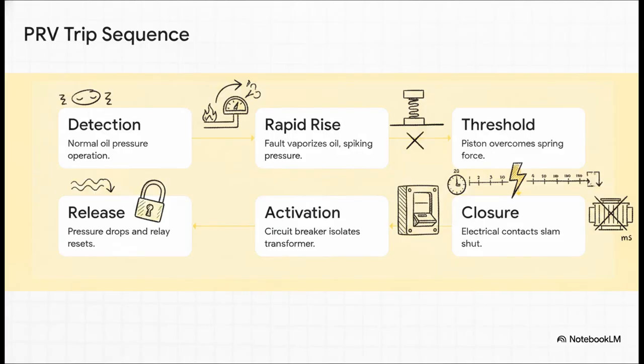Because it's so fast, the PRV has to progress through 6 precise stages in an absolute flash. It starts in a dormant detection state, jumps into action during that rapid pressure rise, and decisively pushes past the spring's physical threshold. Once it crosses that line, boom, the piston slams the electrical contacts shut. That critical contact closure happens instantaneously, usually in just 20 to 100 milliseconds.